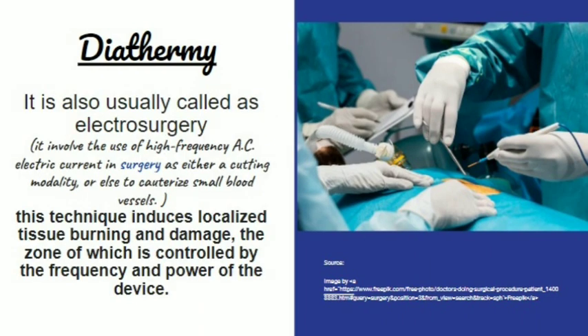Diathermy is also called electrosurgery. It involves the use of high frequency alternating current in surgery as either a cutting modality or used to cauterize small blood vessels. This technique induces localized tissue burning and damage, the zone of which is controlled by frequency and power of the device.